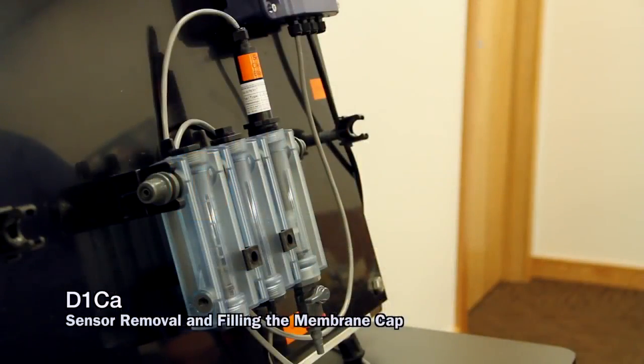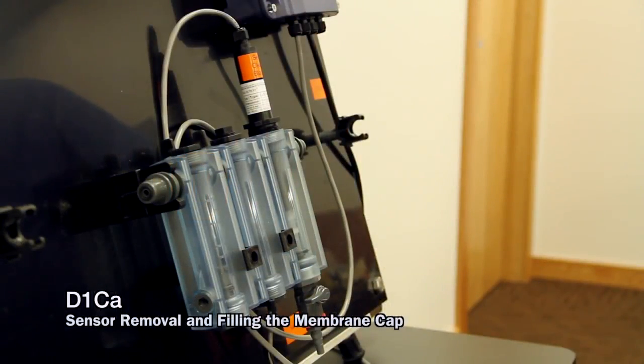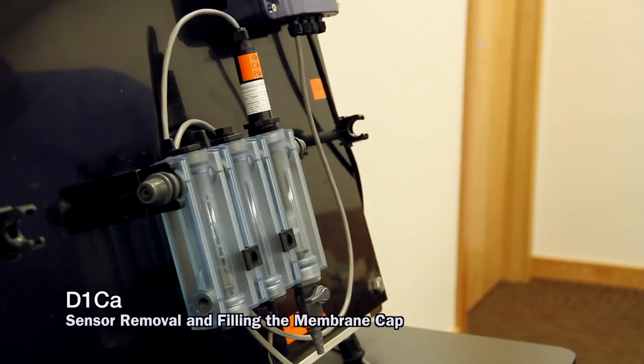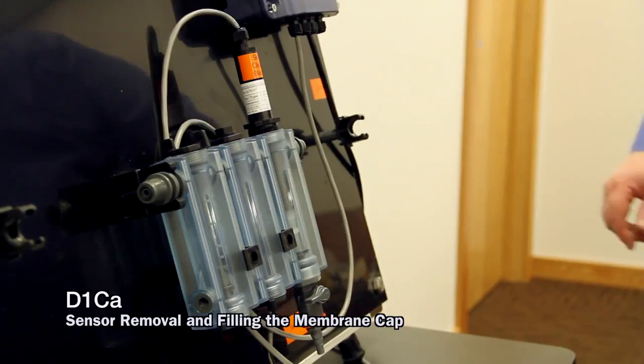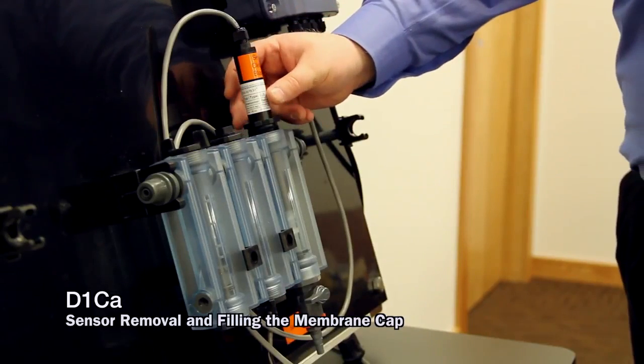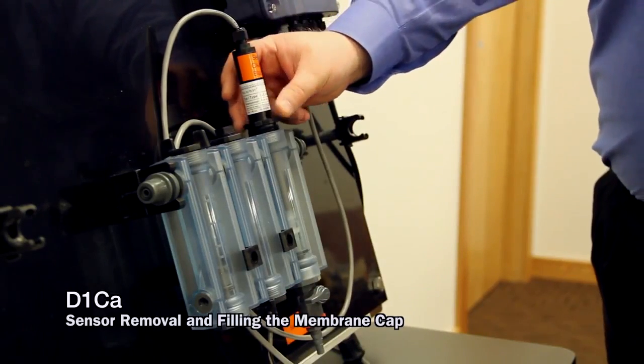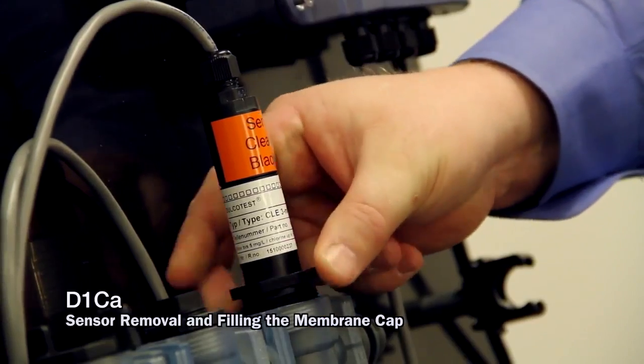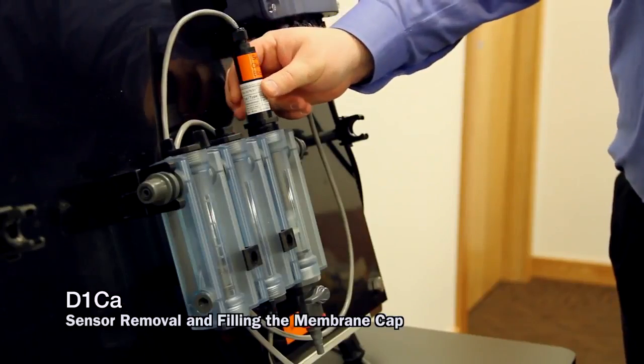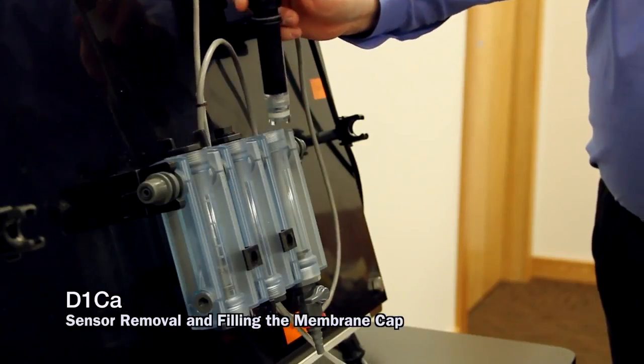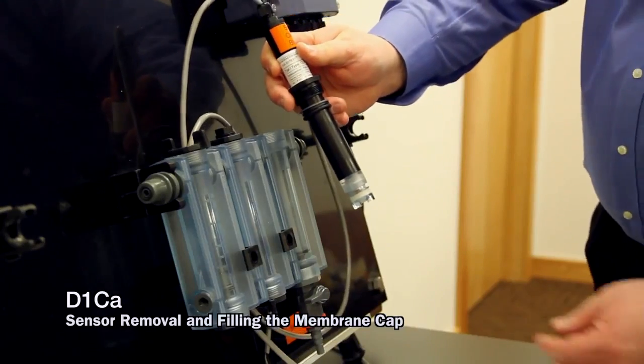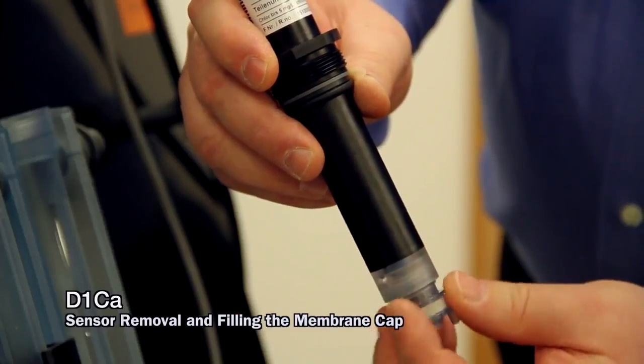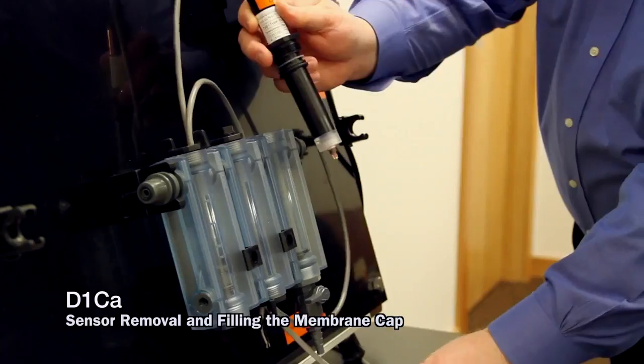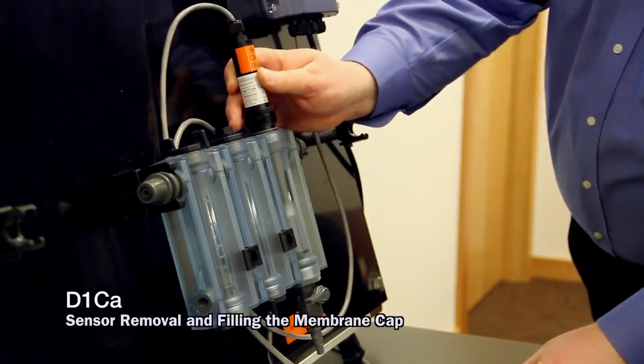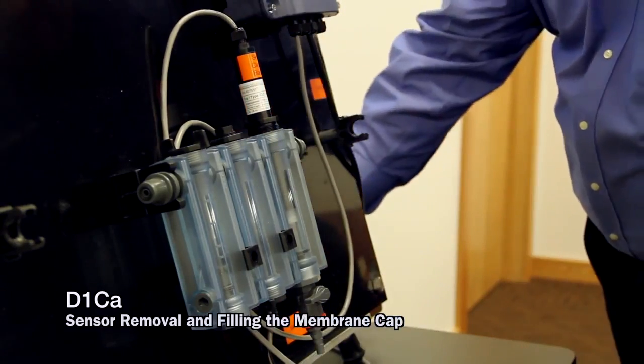This section is to show removing the sensor from the sample line and filling the membrane cap with electrolyte. So we're going to be sure that we don't have flow in our sample line. Loosen the compression fitting holding the sensor in place. Remove the sensor from its sample cell. Remove the membrane cap. I'm just going to place that there for the time being.